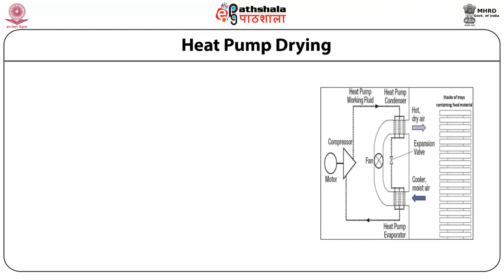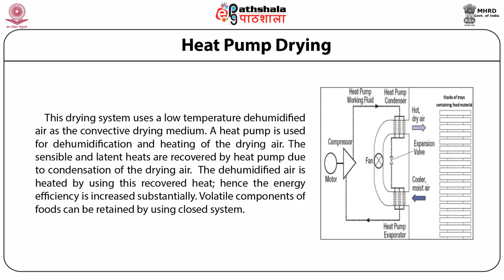The drying system shown here uses low temperature dehumidified air as a convective drying medium. A heat pump is used for dehumidification and heating of the drying air. The sensible and latent heat are recovered by the heat pump due to the condensation of drying air. The dehumidified air is heated with the help of recovered heat, and hence we can achieve high energy efficiency in this process.